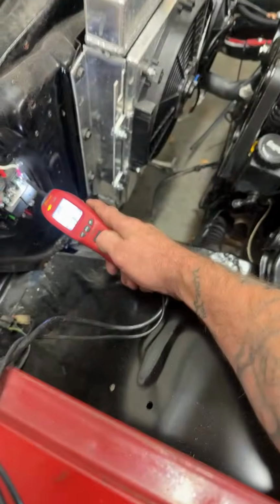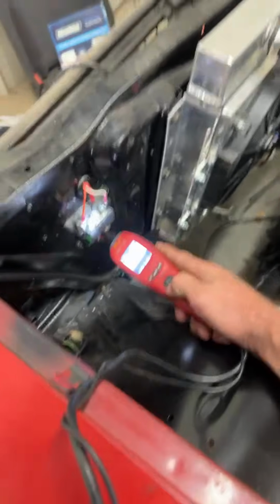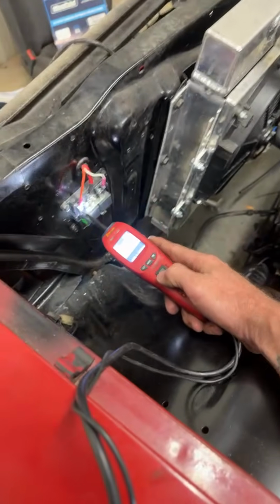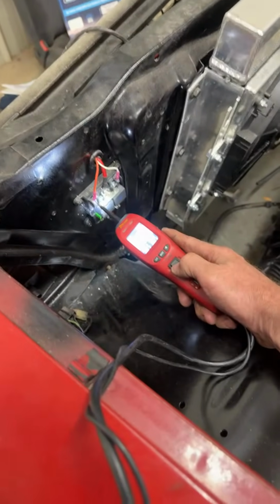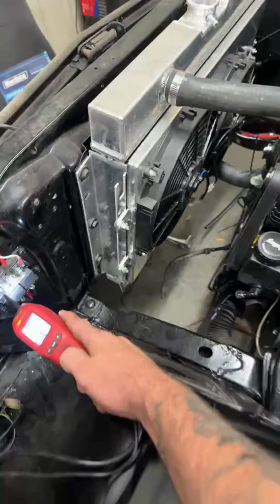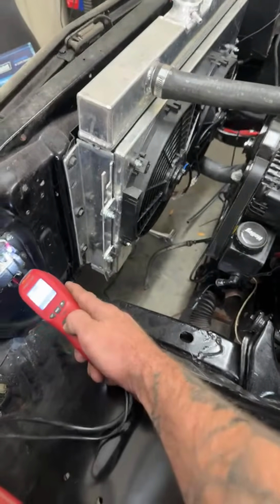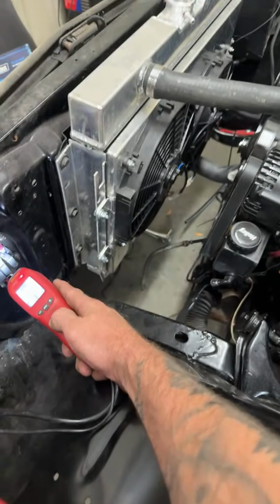So now we got fan 2 on, and I can't do them at the same time because I only got one power probe. But fan 1 comes on at 180, right? Because we got it set in the handheld at 180 on the ground side. And then fan 2 comes on at 190 on the ground side.